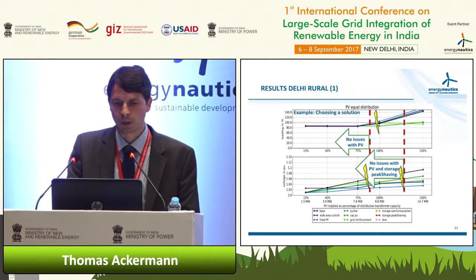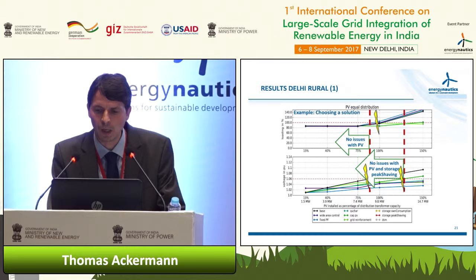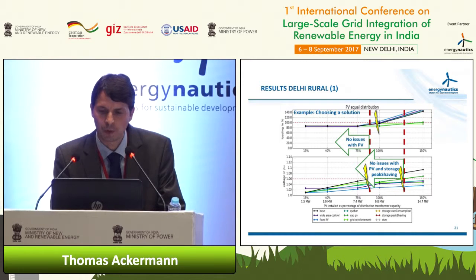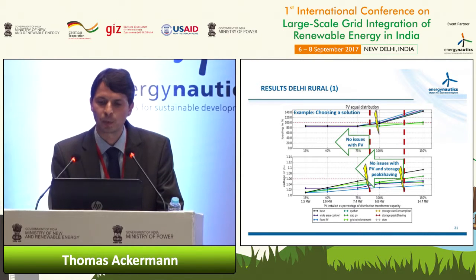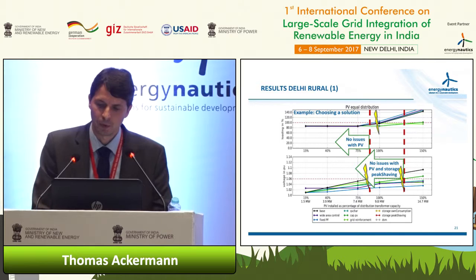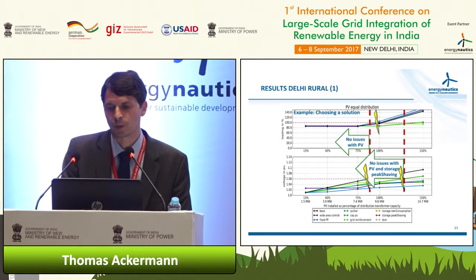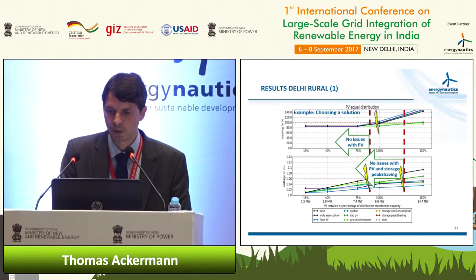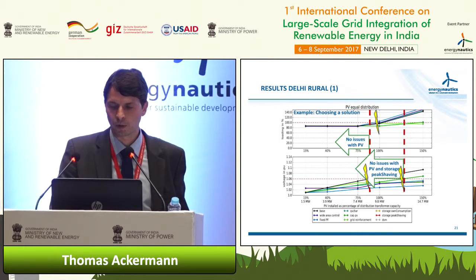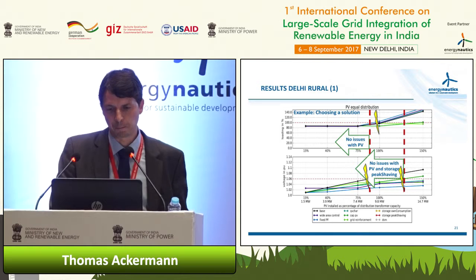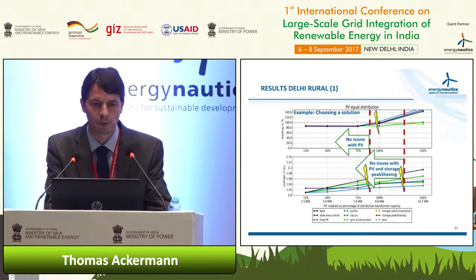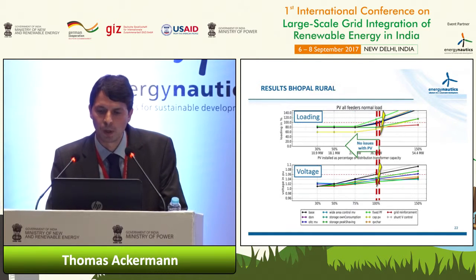And looking at Delhi Rural, we do get a voltage issue here. So this time we can actually extend the limit by using reactive power measures, up to 100% are possible by using, for example, QU characteristic or QV. And for another BHOPAL rural result, we can see again 100% are possible.